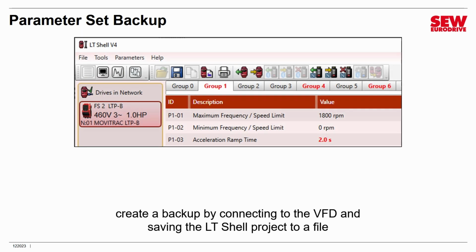Well, of course, you need to be in parameter edit mode. You need to be online with the VFD, and you need to have scanned into it so that its parameters are currently active on the screen. Now, once you've done this, you create the backup just by saving the current LT Shell project.